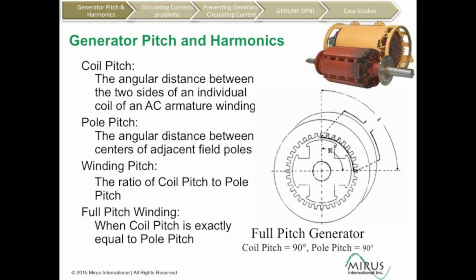So let's start with a brief description of generator pitch configurations and how this generates harmonics. AC voltage is produced in a synchronous generator's armature windings by the generator's rotating magnetic field. Although a perfect sinusoidal waveform is the goal, some distortion will always be present. The configuration of this distortion is influenced by the generator's winding pitch. Winding pitch is the ratio of the coil pitch to the pole pitch, and coil pitch is the angular displacement between the 2 sides of the individual coil winding.